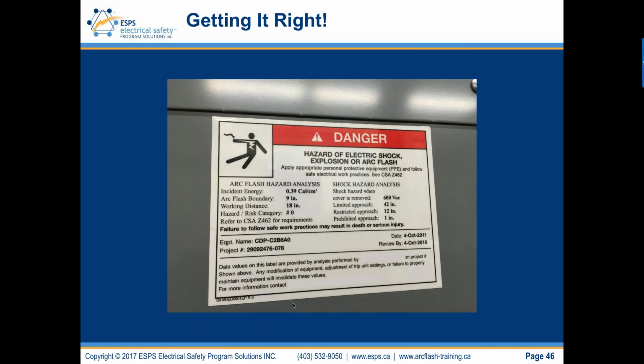The language is basically fear-based language at 0.39 calories per centimeter squared. I could blow on my hand, and that's probably going to be 0.39 calories. So again, this is an example where the labels were conservatively applied because a lawyer or a marketing guy said, put that label on. Or the lawyer advised the engineer, due to liability, to just put everything on the label and push the liability to the employer. The employer hired the engineer to manage liability for them, not to push it on them.